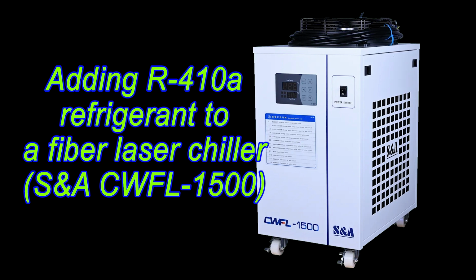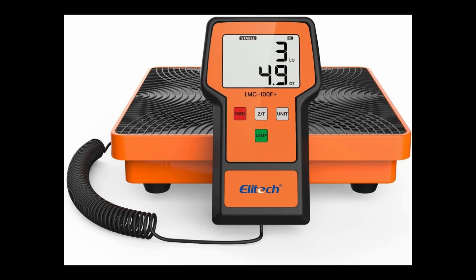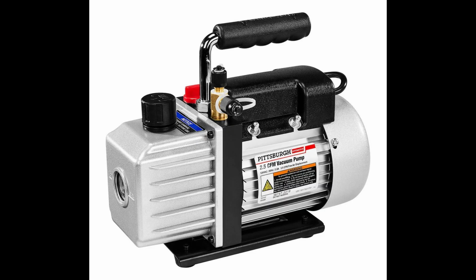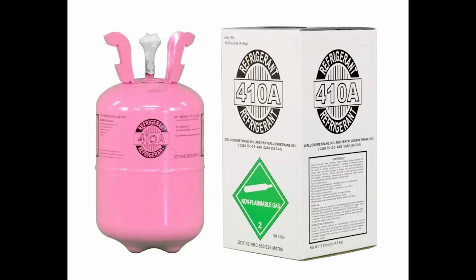One of the conditions was that they had to ship it via air without refrigerant, which is R410A. That wasn't a big deal, since I had the equipment to do it. You need a scale, a vacuum pump, and of course a tank of R410A, which you can buy online.